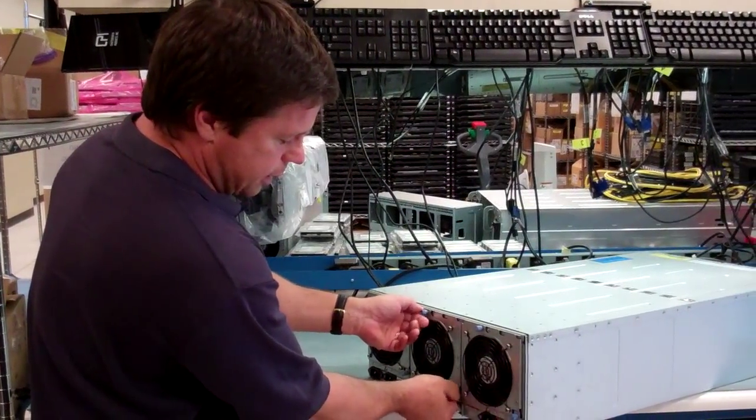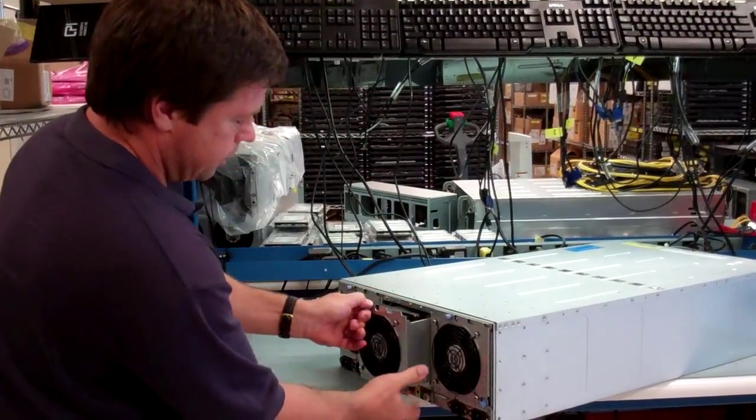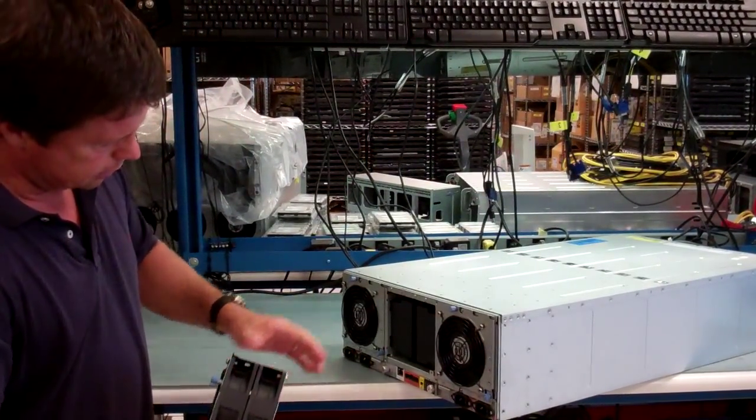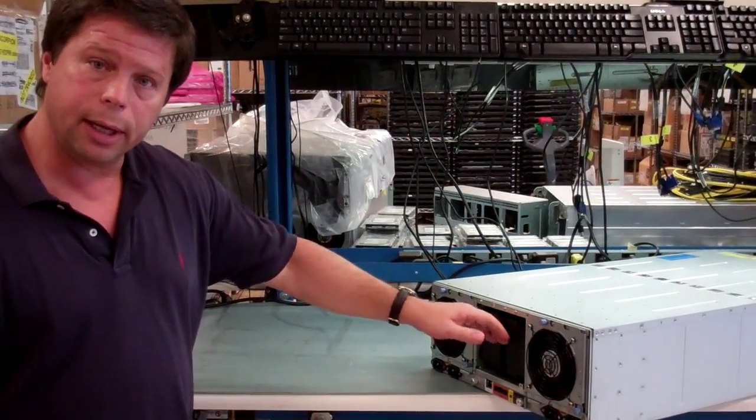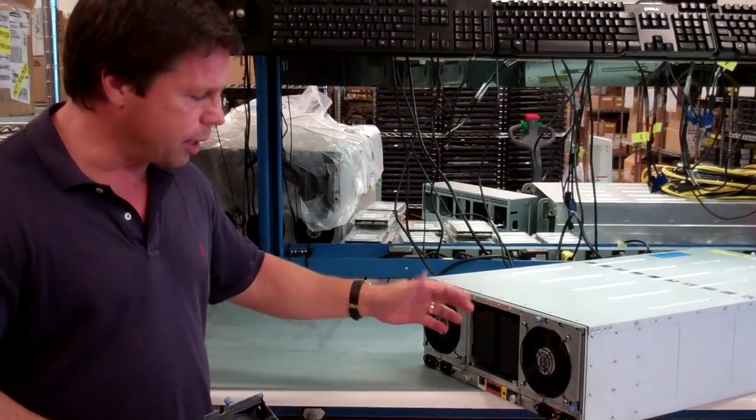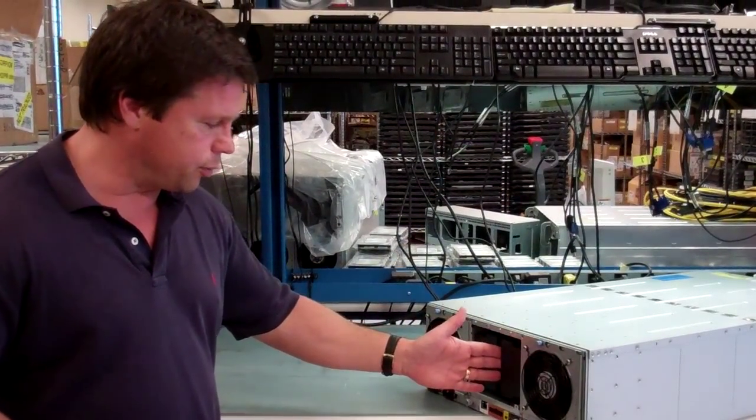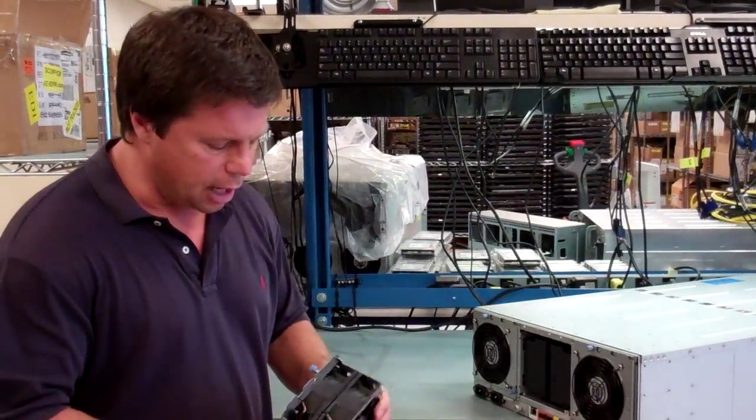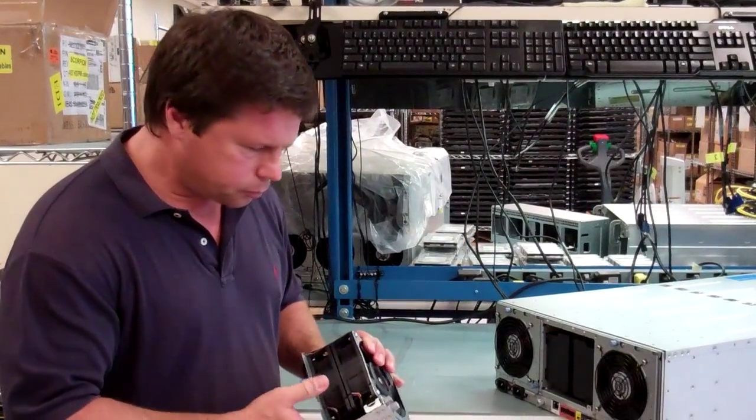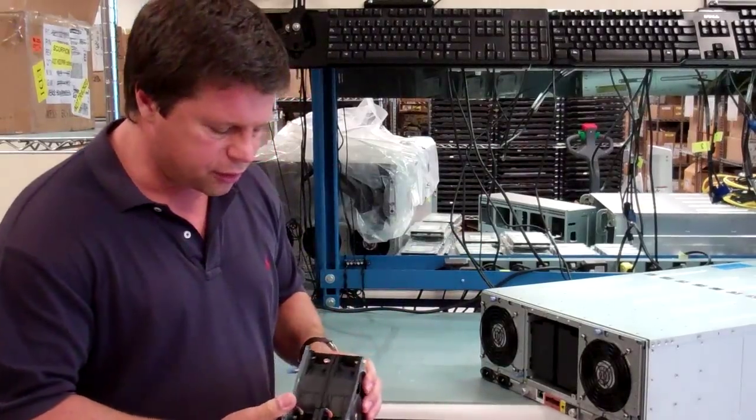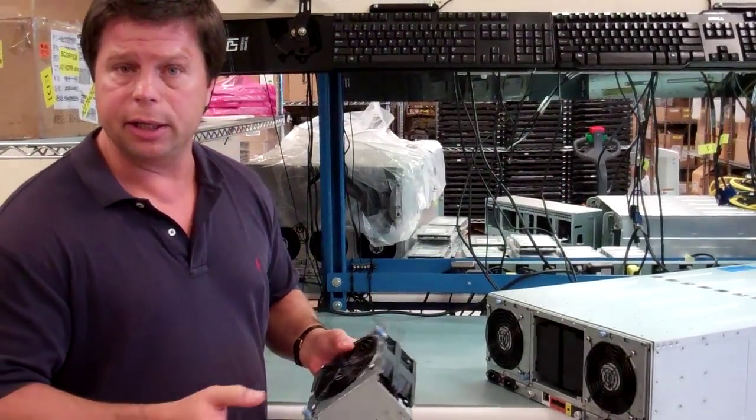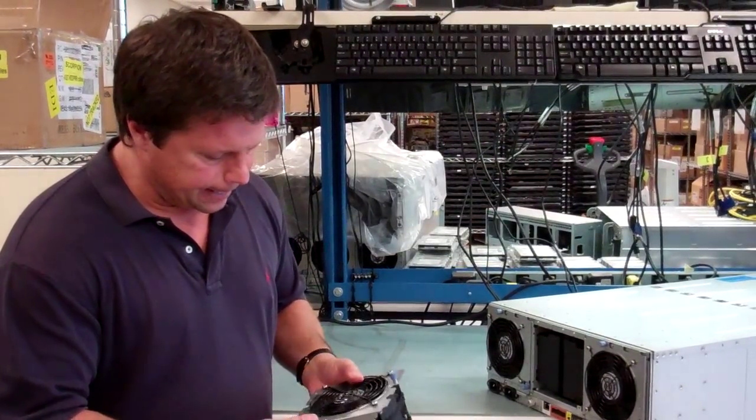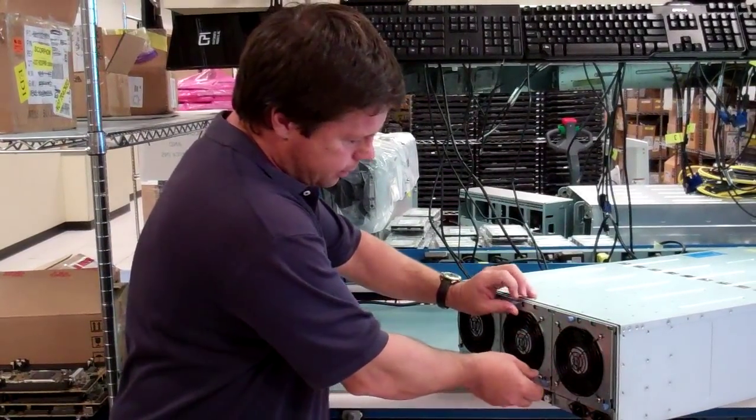As far as servicing, the fans, very easy, tool-less. The fans come out like so. The equipment continues to run. We have little louver doors that will maintain some pressurization so that we don't get too much leakage through this gap. And we can still keep things running cool inside. We have dual fans. So we have three by two, a total of six fans provide for fan redundancy for just about any configuration we have here. The fans go back in.